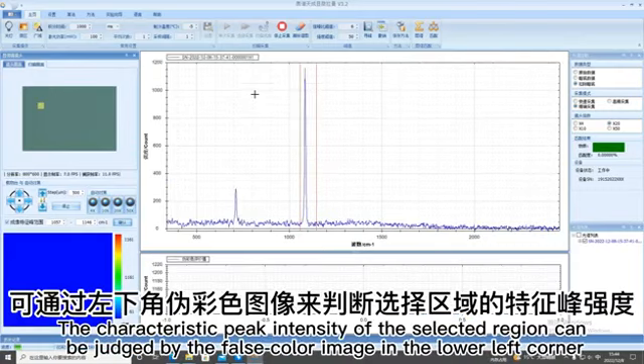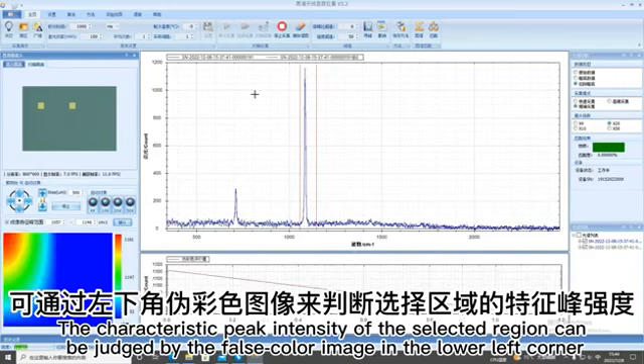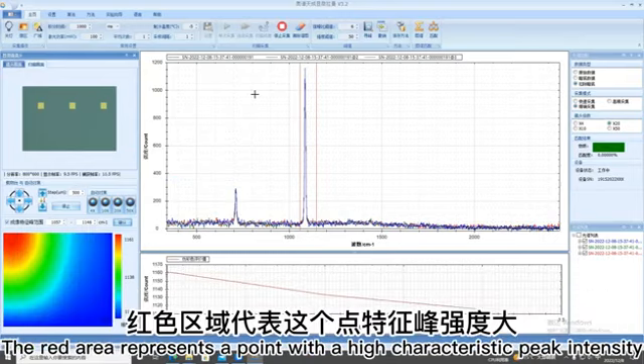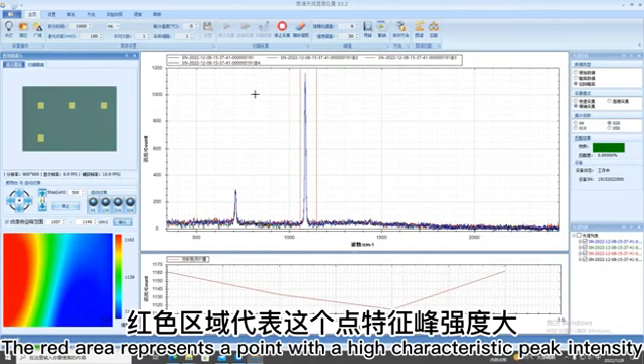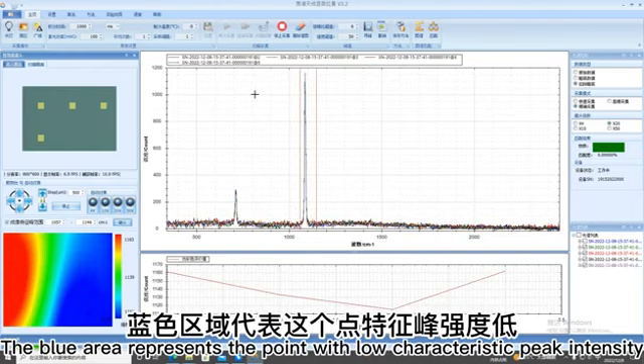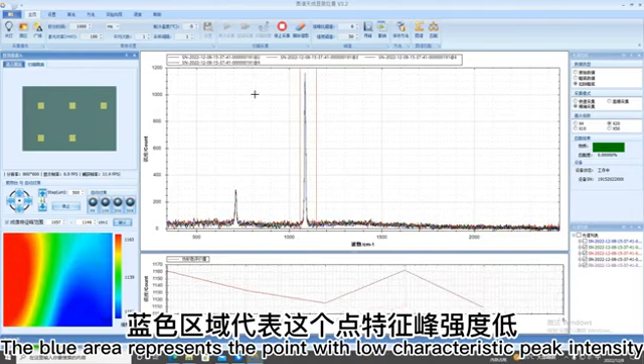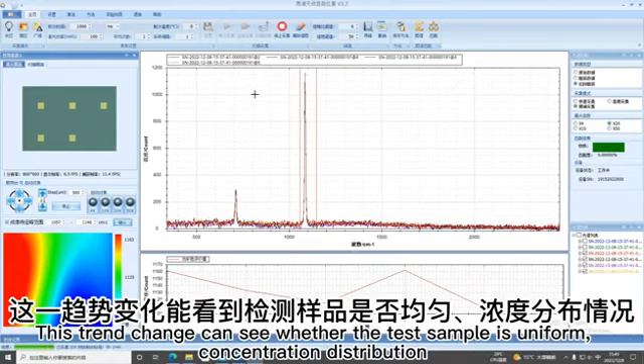The characteristic peak intensity of the selected region can be judged by the false color image in the lower left corner. The red area represents a point with a high characteristic peak intensity. The blue area represents the point with low characteristic peak intensity. This trend change can show whether the test sample is uniform. Concentration distribution.